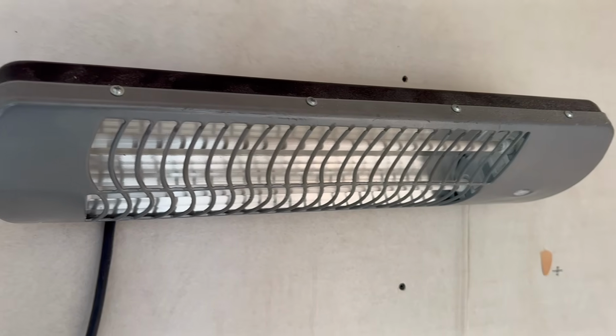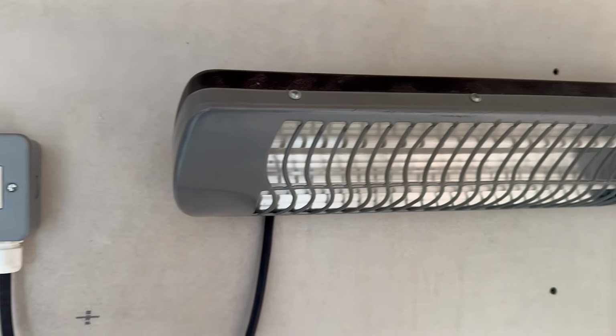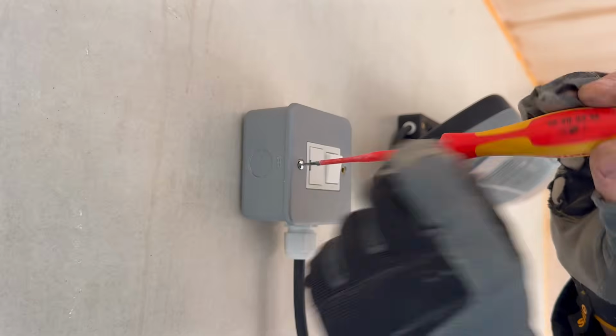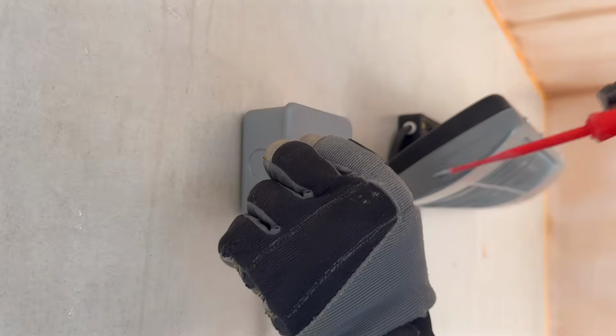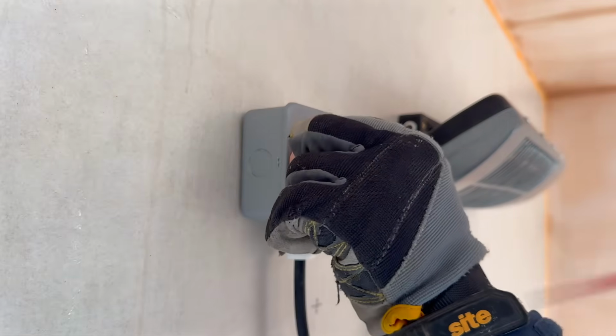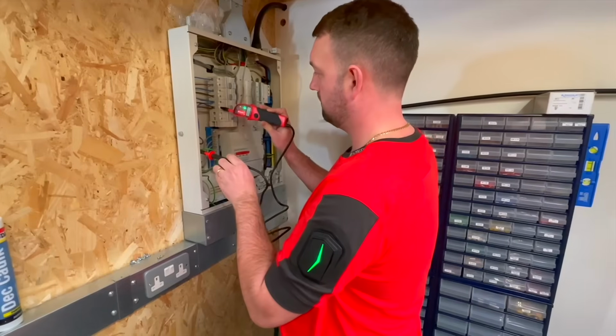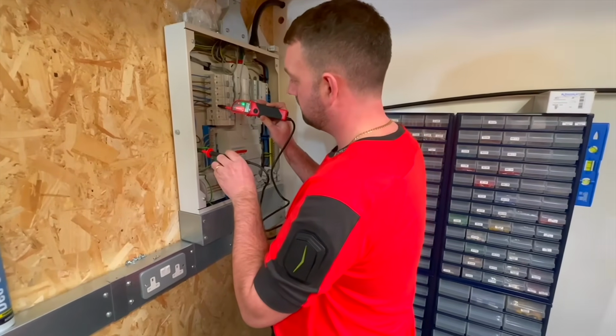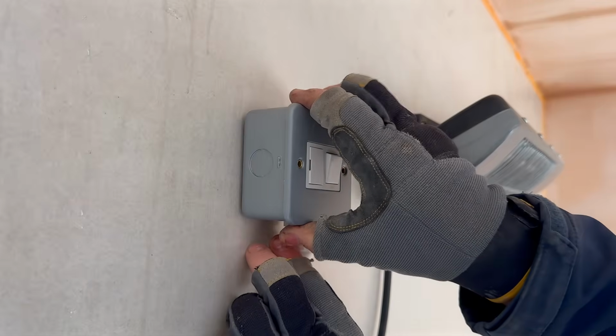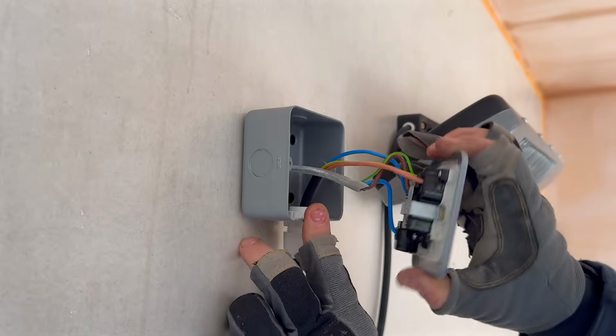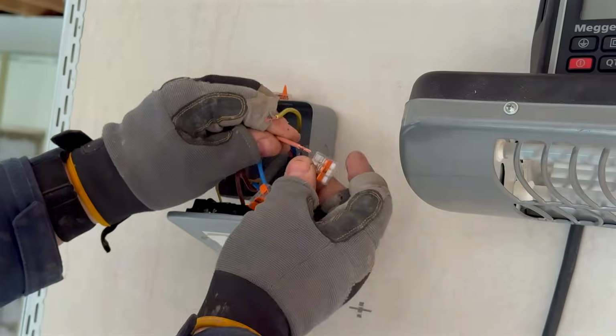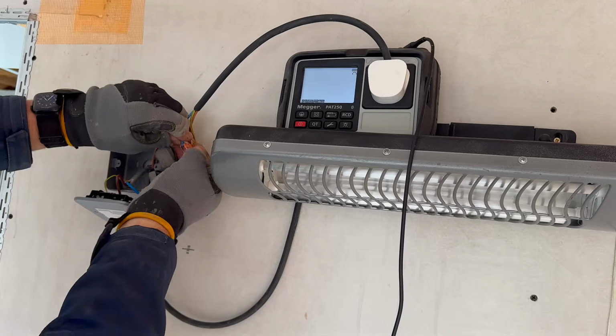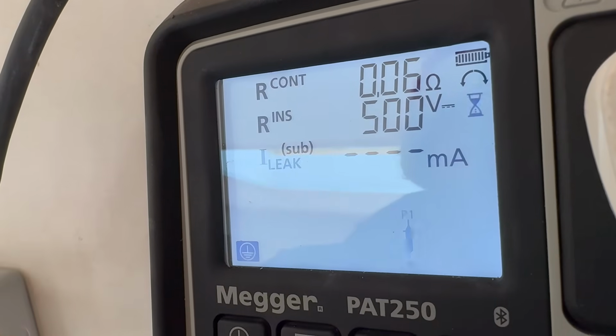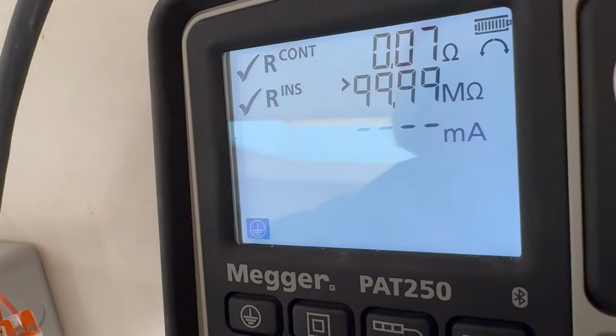The last appliance to test is this heater, which is fixed to the wall and controlled from a switch fuse spur. This is fixed equipment, and on this job it's not forming part of the fixed wiring maintenance regime, so we need to test it. This is where training and experience matters as safe isolation is needed. Once switched off, we unscrew the front plate and disconnect the CPC of the flex. We can now, using the probes and this breakout lead, test the protective conductor. I now put the probes on the line and neutral and carry out the IR test.